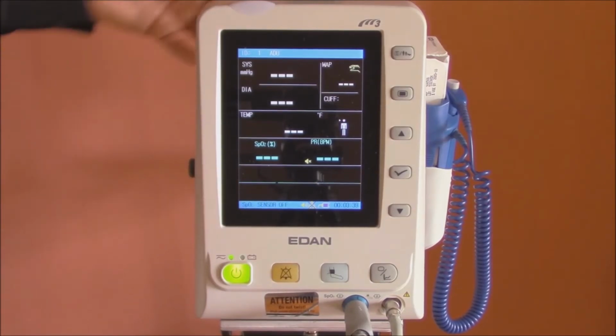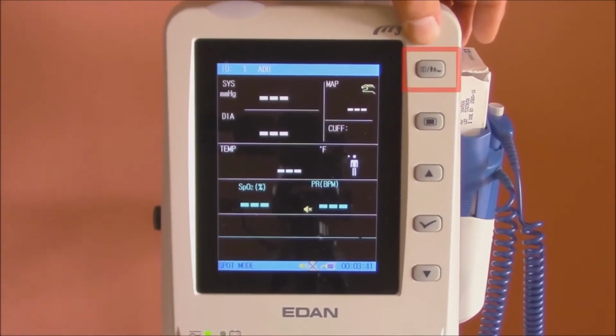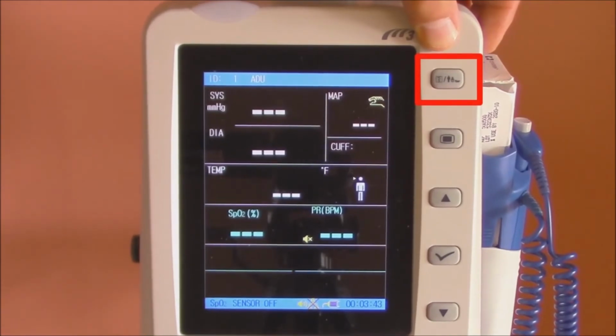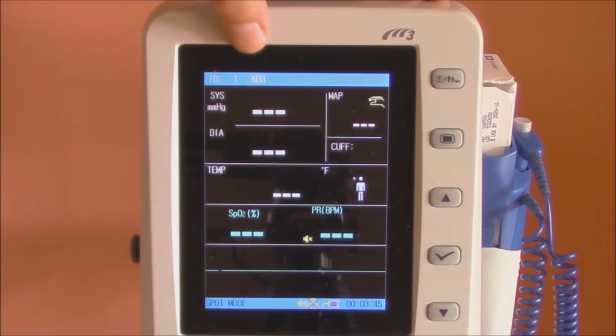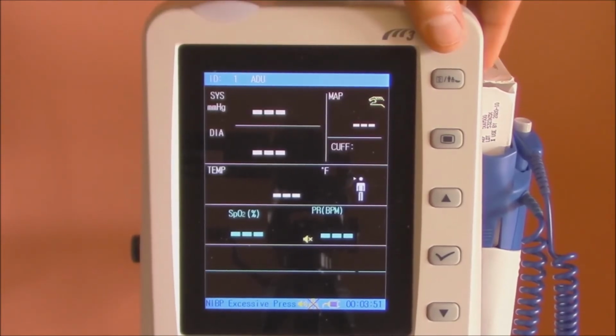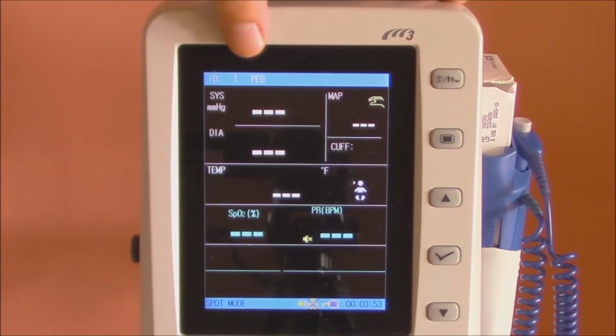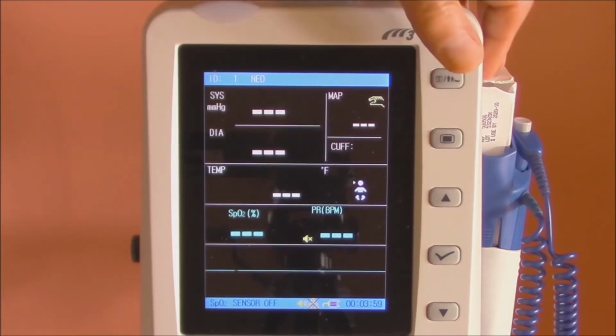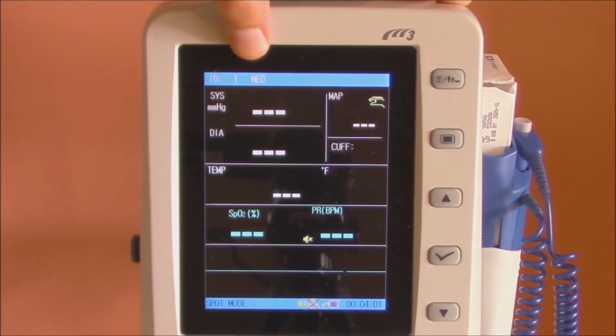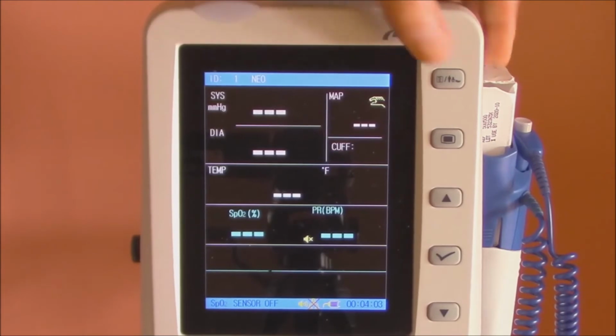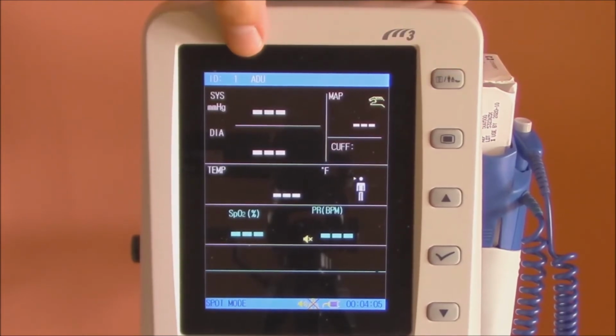Starting at the top of the unit, the first button is the Patient Size button. This patient size abbreviation is shown in the blue status bar at the top of the display. ADU stands for Adult. If the Patient Size button is pressed, the Vital System's configuration will change from Adult to PED for Pediatric. If pressed again, the configuration will change to NEO for Neonatal, and then if pressed again, the patient size will loop back to Adult.